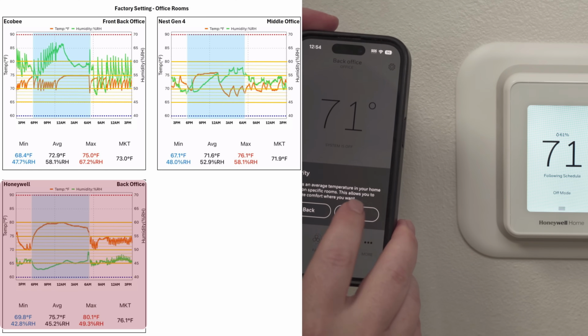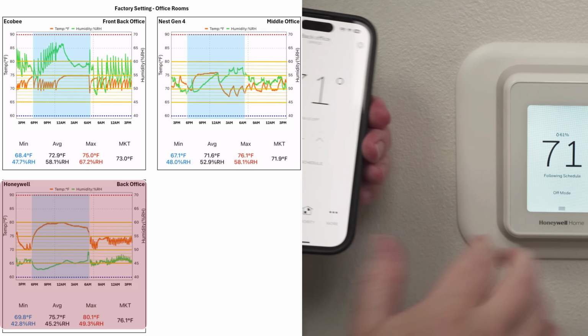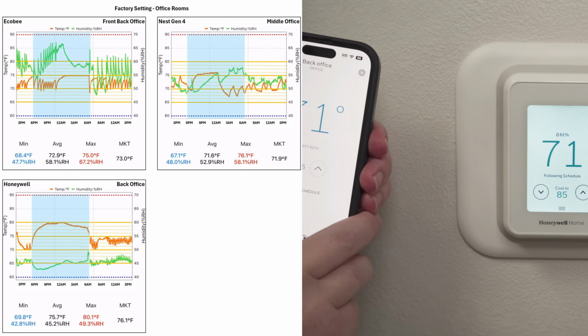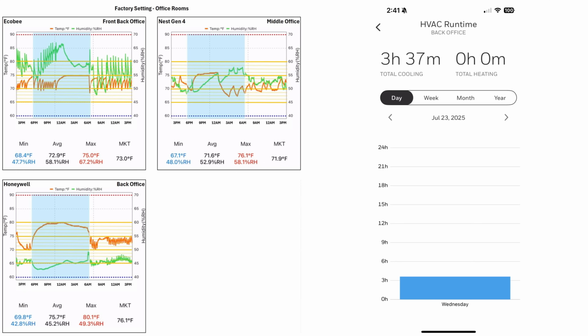Once again, all I did was set it to cool mode, lower the temperature to 72 degrees, then prioritize the room sensor. And no other changes were made. On the right, I have our Honeywell runtime report, which is super basic, and there's also a 2-day lag before you can get a hold of this report. So you can see around 3 p.m. I prioritized the room sensor, and that's why we see the temperatures drop from 76 degrees all the way down to 71. And at 6 p.m., the thermostat was scheduled to raise the temperature to 85 degrees.